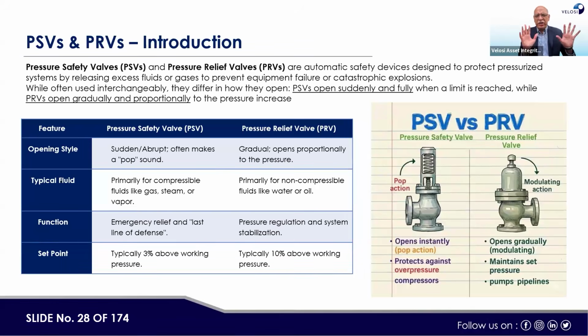So in general, the set point is generally 10%. But my reference says that for gas service, a range of 3% above, or for liquid service, a range of 10% above the working pressure or design pressure is generally allowed. So in general, PRVs open gradually, whereas for gas service, PSVs open as a pop-up or sudden opening. They function as both emergency relief and pressure regulation or system stabilization.